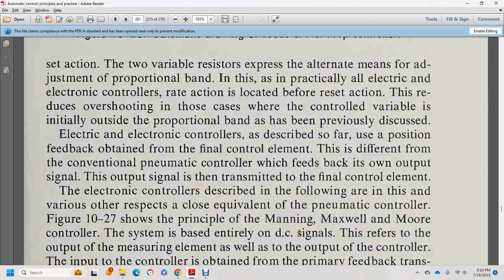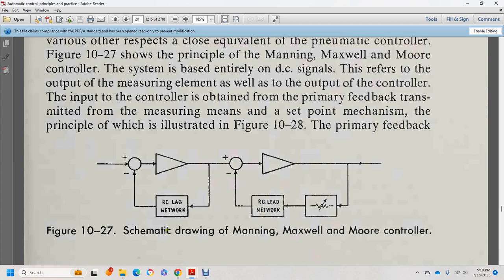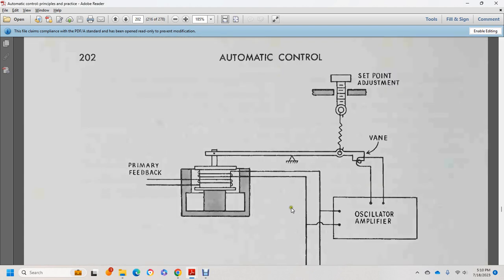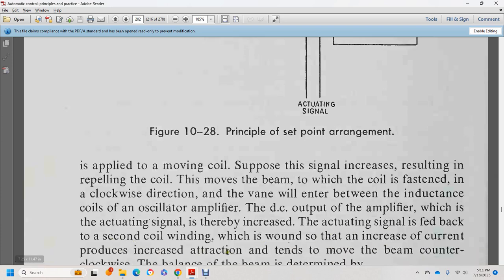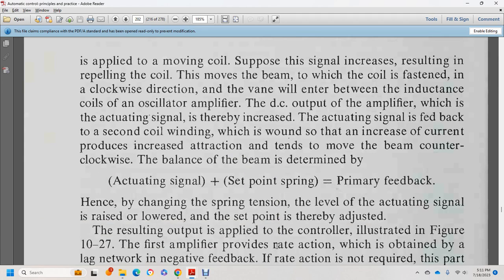The output of the measuring element and the input of the controllers provides the primary feedback transmitted from the measuring means. The set point mechanism principle is illustrated in figure 10-28. The RC lag network and RC lead network are shown. The set point adjustment vane, primary feedback, oscillator, and amplifier produce the actuating signal. The actuating signal is applied to move the coil — the coil moves the beam, and the vane enters between the inductive coils of the oscillator and amplifier. The DC output of the amplifier serves as the actuating signal fed back to the secondary coil, increasing current. This tends to move the beam counter-clockwise. The beam is balanced by the actuating signal, the set point spring, and the primary feedback. Lowering the actuating signal rate allows adjustment of the set point.